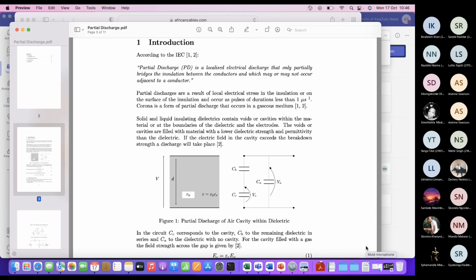All right, partial discharge. It's a localized electrical discharge that only partially bridges insulation between conductors. So that's key. It's not a full discharge. It's not a disruptive discharge. So it's a very small discharge in only part of the insulation. So they are a result of local electrical stress.